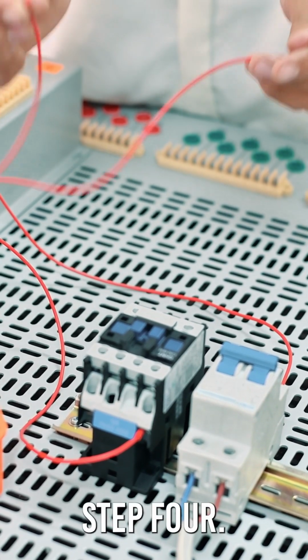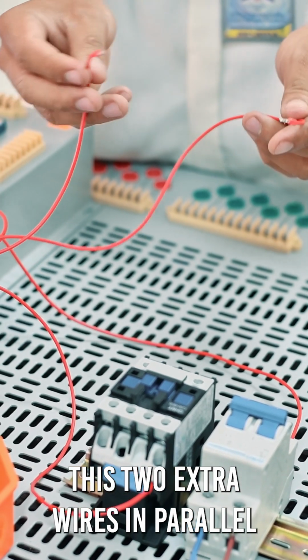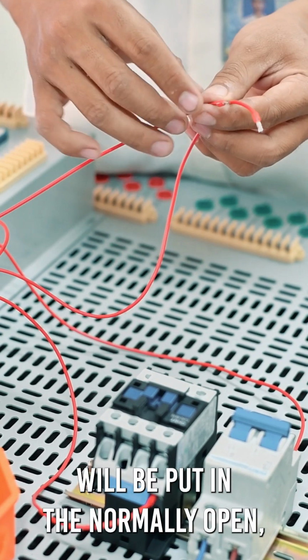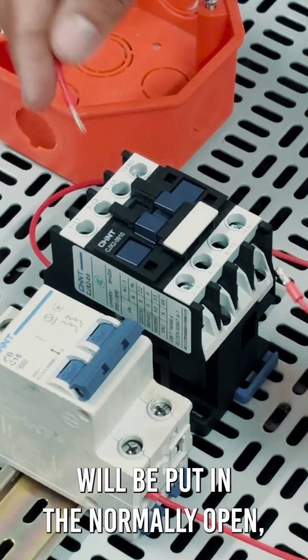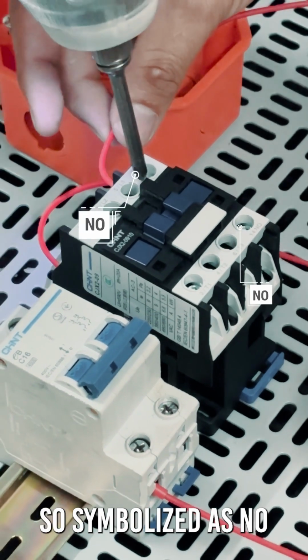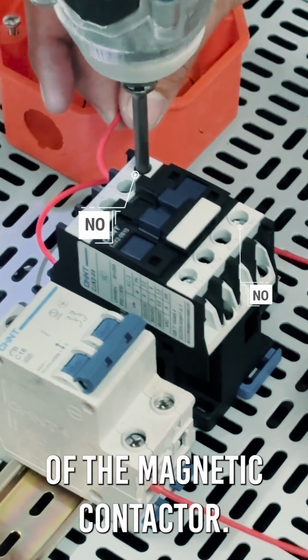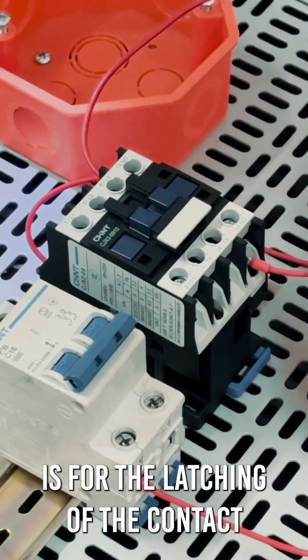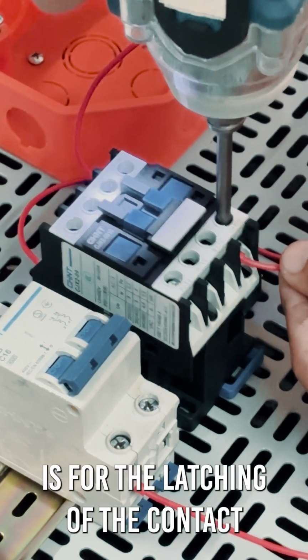Step 4: These 2 extra wires in parallel with the start button will be put in the normally open (NO) terminal of the magnetic contactor. Its purpose is for the latching of the contact of the start button.